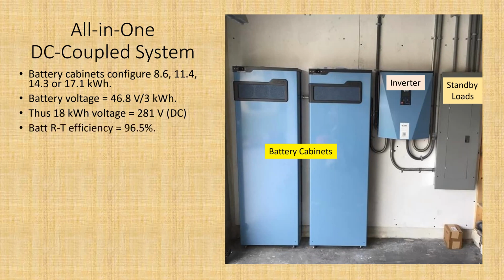Battery round trip efficiency is about 96.5%, is what the manufacturer claims. So you know right away it's lithium. I think this is lithium cobalt, I don't remember exactly. There are 6 different lithium technologies, and this is one of the favorites for use in PV systems. Continuous battery power for one of these cabinets is 6.7 kilowatts. We were talking about that before, that you're limited to the amount of power you can draw out, not just the number of kilowatt hours, but the number of kilowatts. So if you're powered up at 17.1 kilowatt hours, in other words, you've got 6 of the packages in the blue case, then you can pump out 6.7 kilowatts. This particular system then obviously can do 13.4. And that will light up your stove pretty well, and it will run an air conditioner, and it's not a bad system for whole house backup with that kind of kilowatt hours.